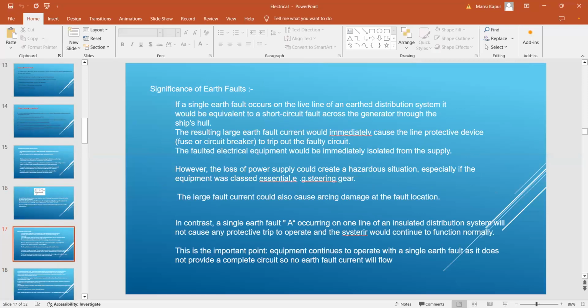What is the significance of earth fault? If a single earth fault occurs on a live line of an earthed distribution system, it would be equivalent to a short circuit, a fault across the generator through the ship's hull. The resulting large fault current would immediately cause the line protective device, such as your fuse or circuit breaker, to trip out the faulty circuit.